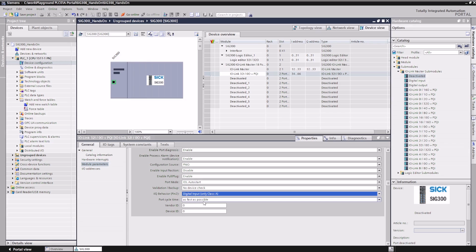In addition to the settings of the digital signals for PIN2 and PIN5, the IO-Link validation can also be set here. In this example, we'll set up the IO-Link port to use the IO-Link data storage feature. Doing so backs up all device parameters for easy device replacement.